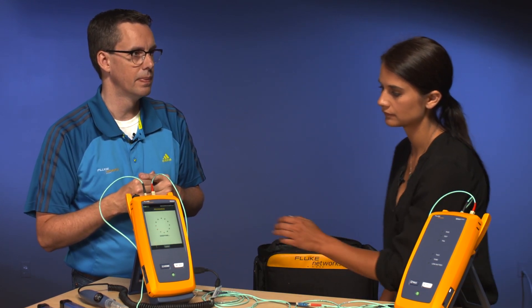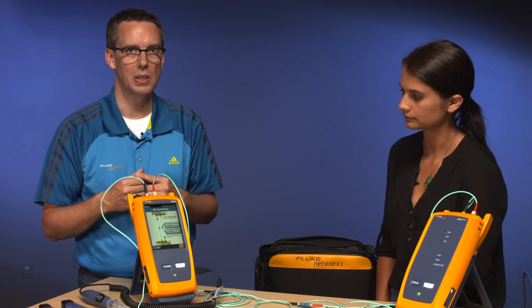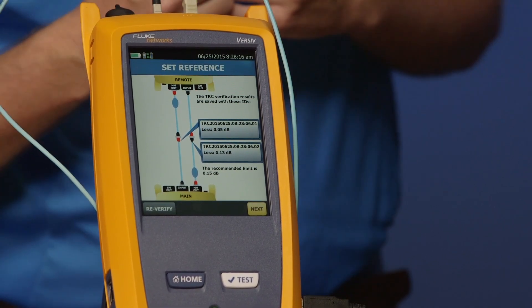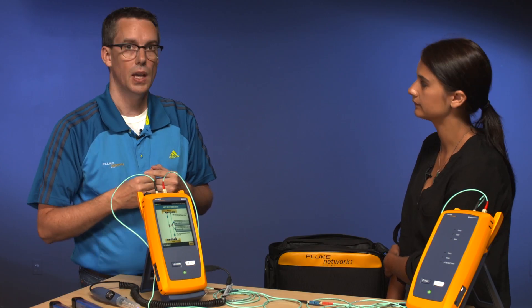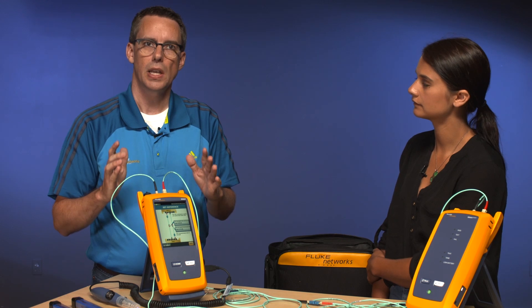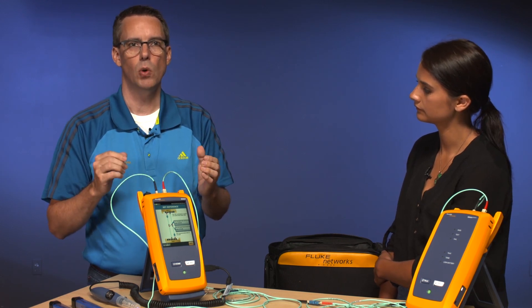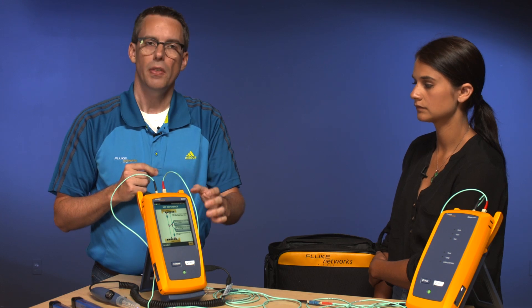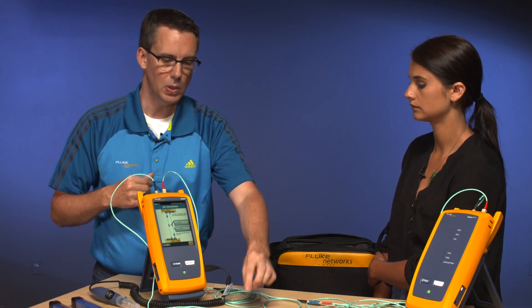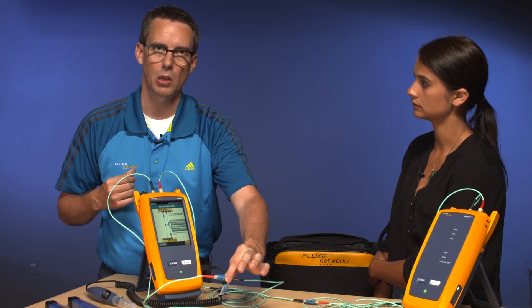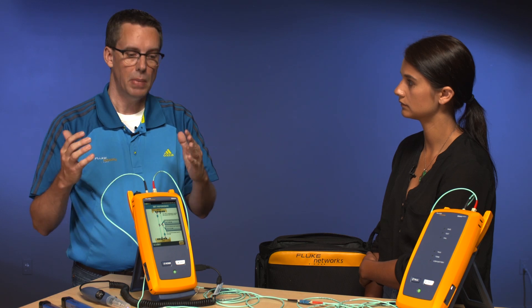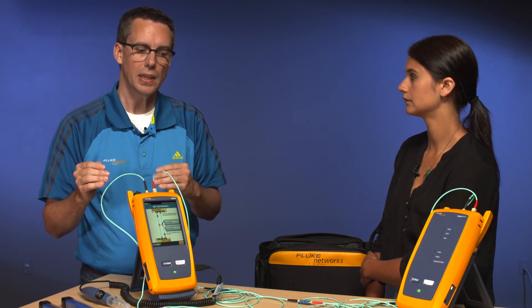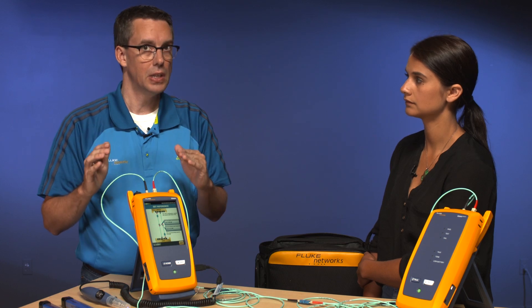Go ahead and tap TRC Verification. This takes about three seconds — certainly a lot quicker than the DTX. We now have our TRC verification results. The loss values are 0.05 dB and 0.13 dB — that's fantastic. The international standards say for multi-mode it needs to be better than 0.1 dB and for single mode better than 0.2 dB — and that's also now a requirement in ANSI/TIA. The tester sets a soft limit of 0.15 dB to account for variability of adapters in the field. It passed, meaning we have good test reference cords. When we start making measurements on the cabling system, if we see failures it's not because of poor test reference cords — it's because there's something wrong with that cabling system.